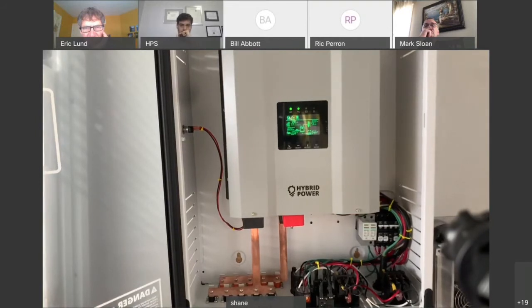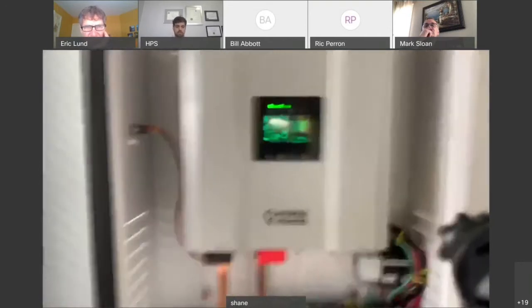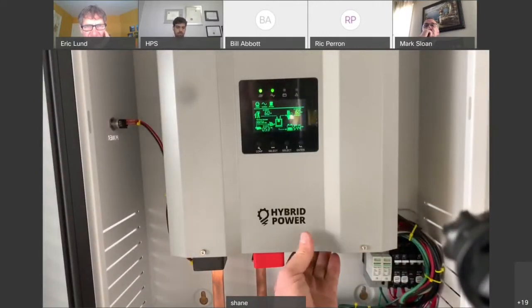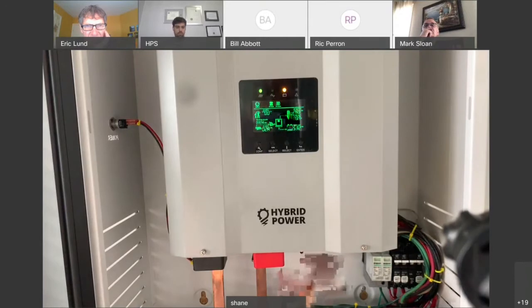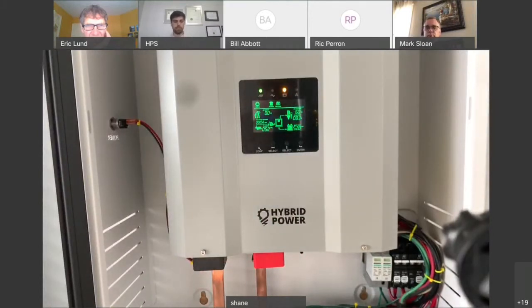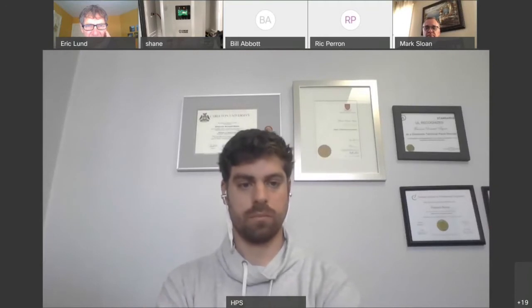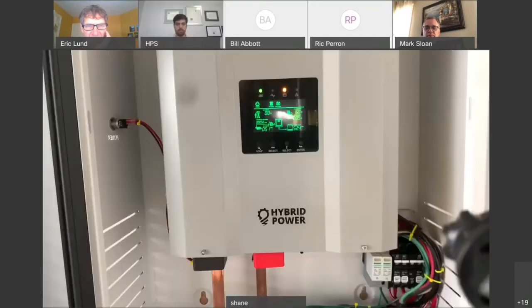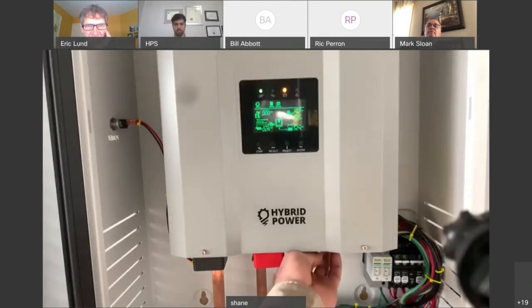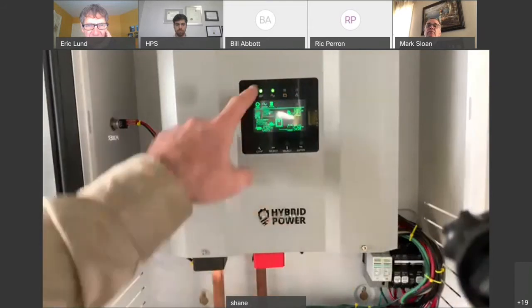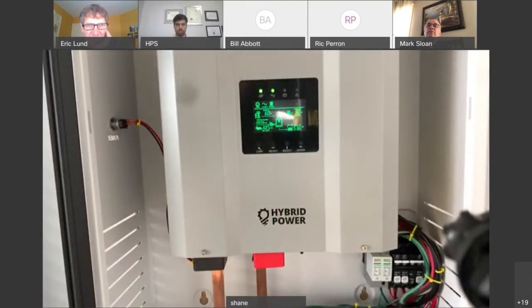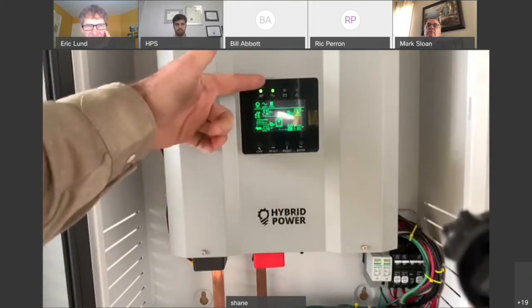You probably can't see or hear anything different, but the fan is on and the elements are going right now, and I can feel the heat. To show you how quick this is, I'm going to kill the charging circuit and go straight to DC bypass or DC mode, and it's still going to run that 5 kilowatt heater. You can see we're using 84% of our rated capacity on our inverter. We have 4 batteries in parallel right now, and we're pulling 23 amps per battery. So then I'll go back. Now let's say it hits the low voltage point and the generator starts up, gives it the proper charge or warm-up time. AC comes back on, and it transfers again. There's no bump in the power. The fan stayed going and the element. We're back on AC mode.